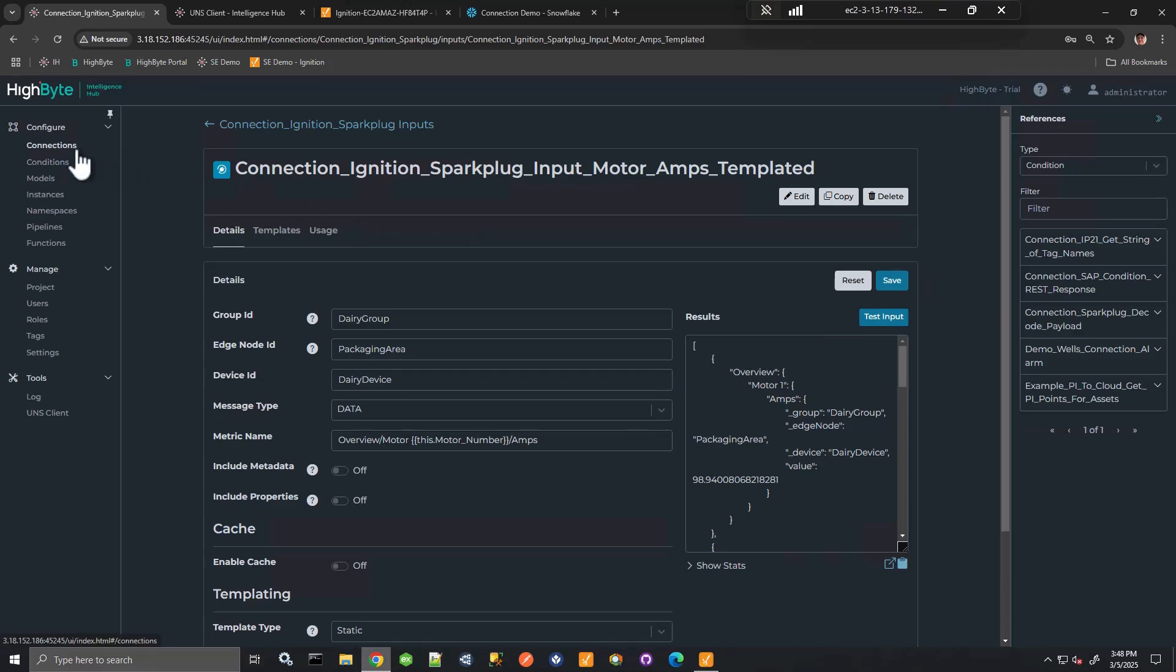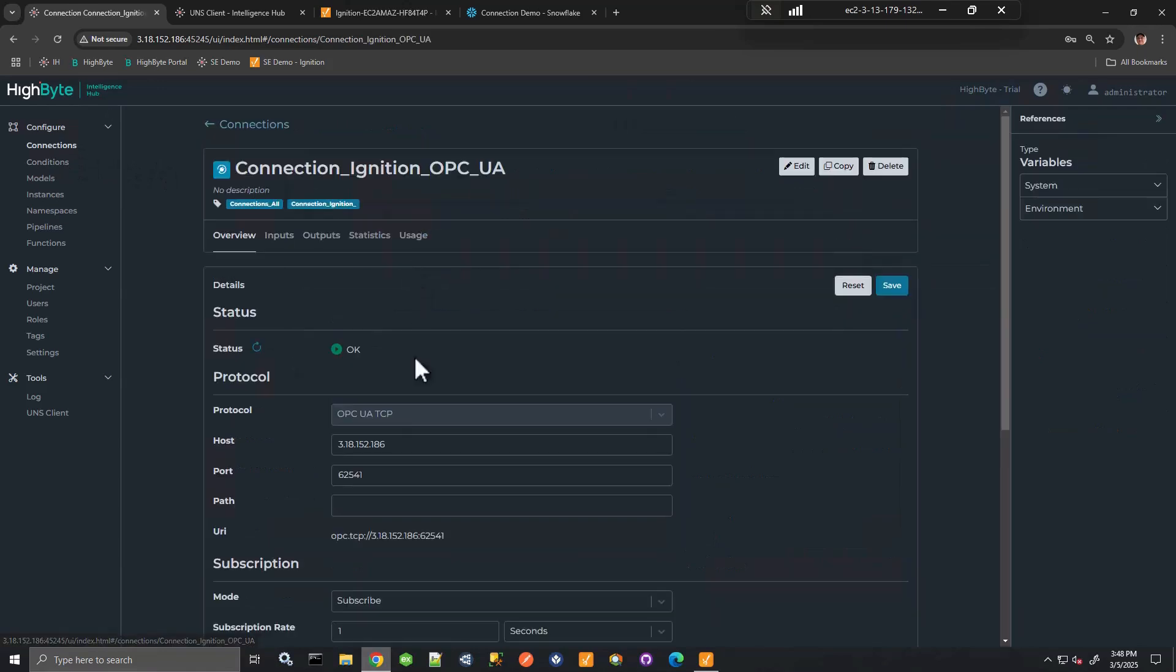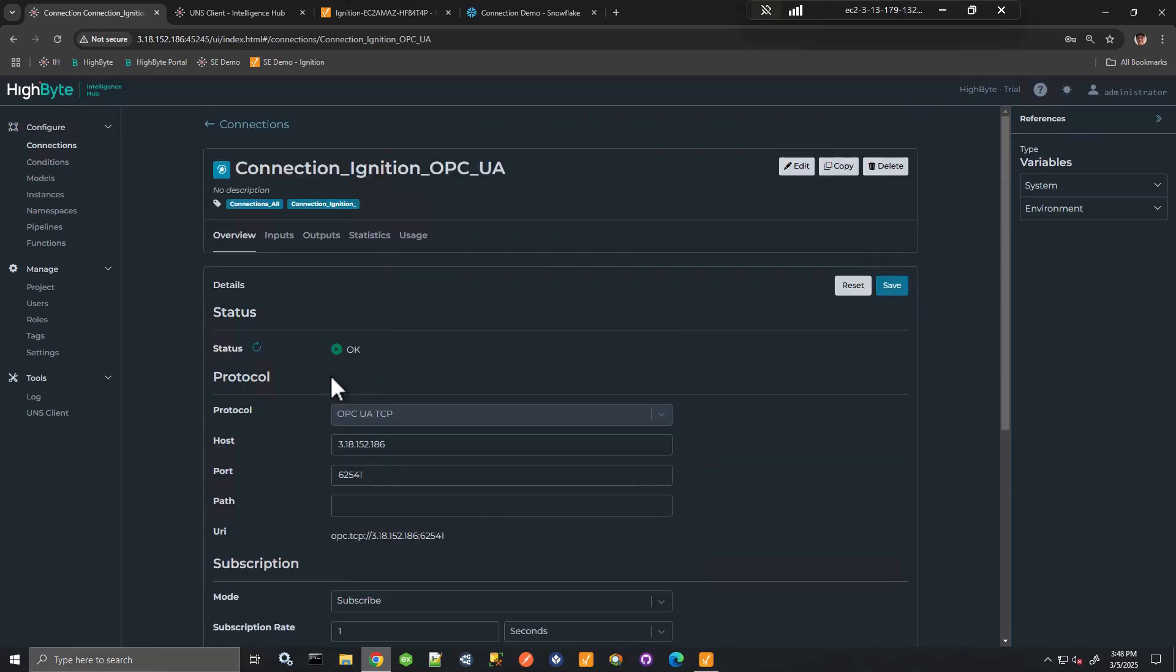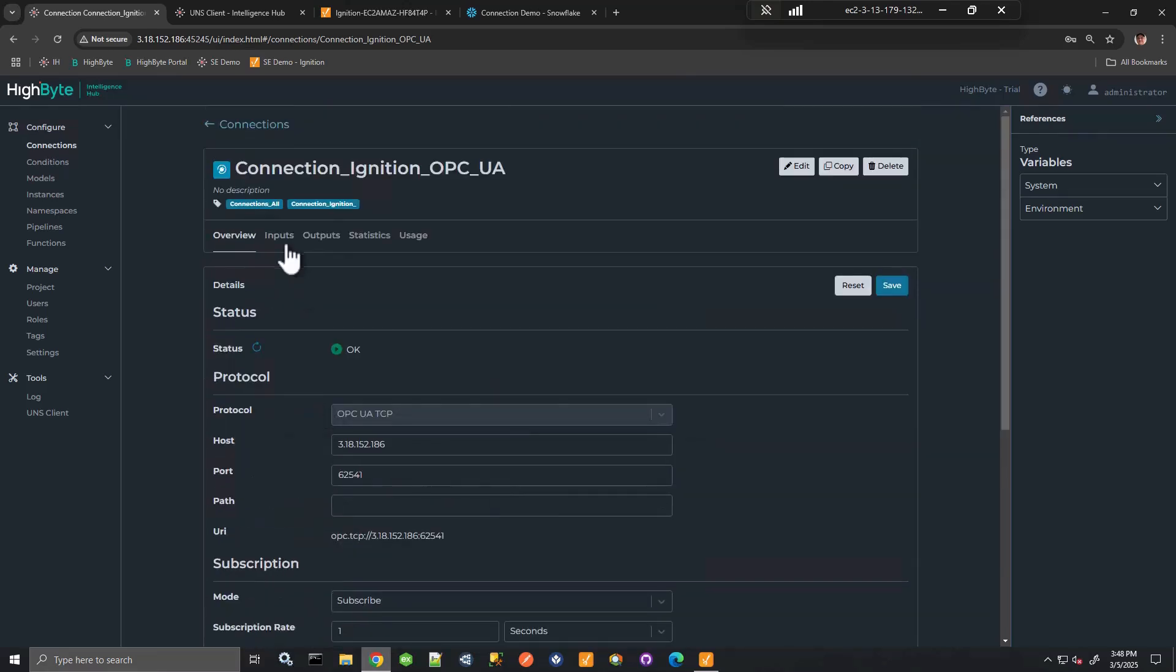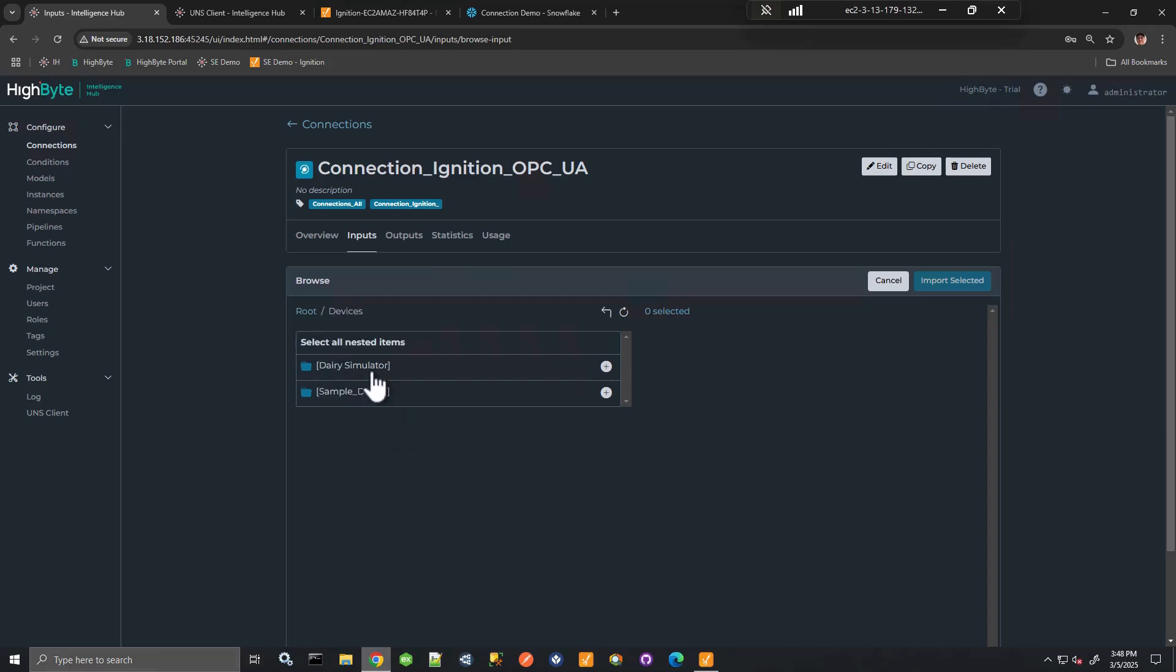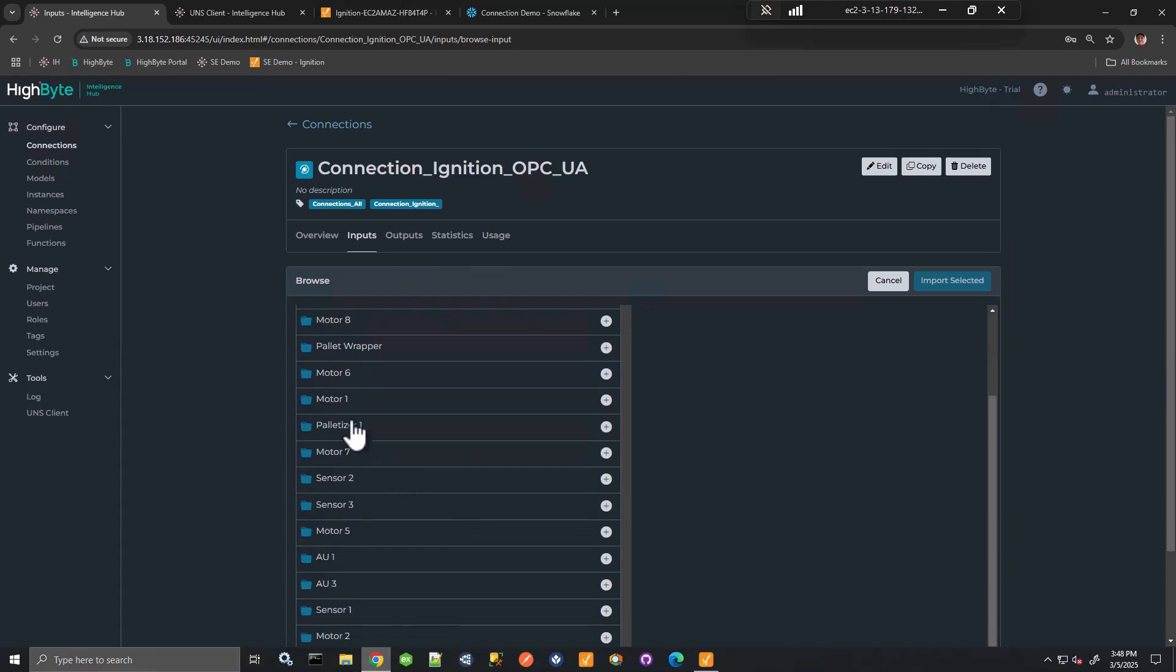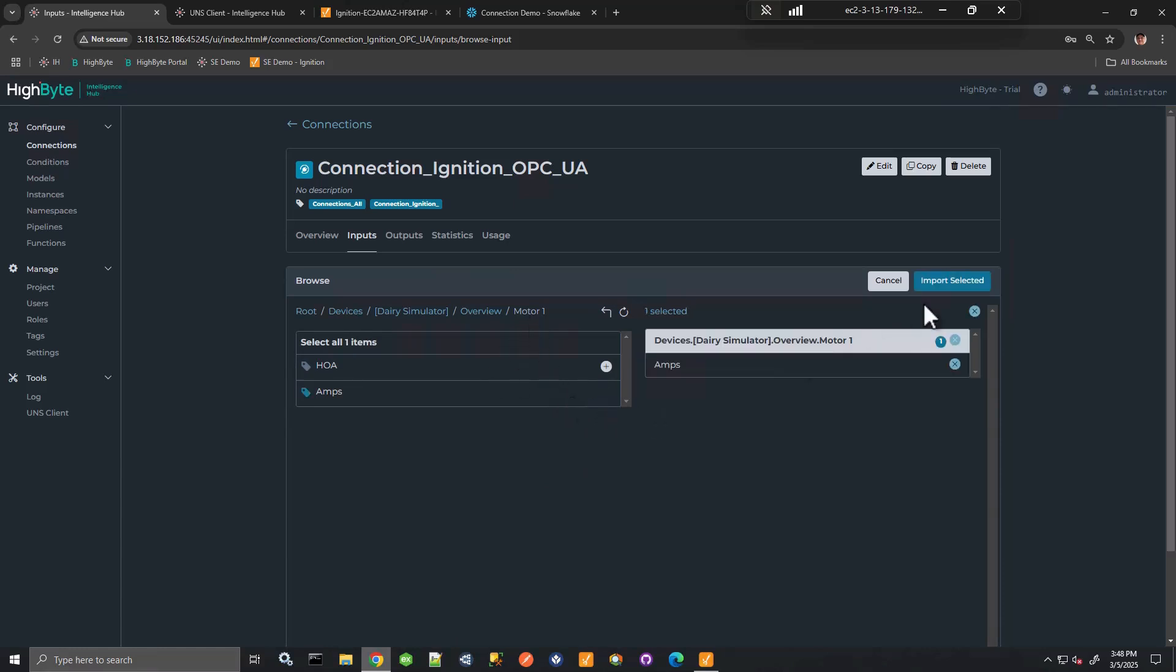We can also obtain data from Ignition with OPC UA. So here I have a connection to Ignition over the OPC UA port. This is just anonymous, but we can define the security here. I would have the ability to browse the namespace. So here I have my dairy simulator and I can browse, maybe pull back a tag for a motor one amps or even a branch as well.